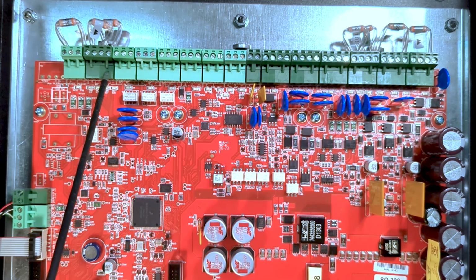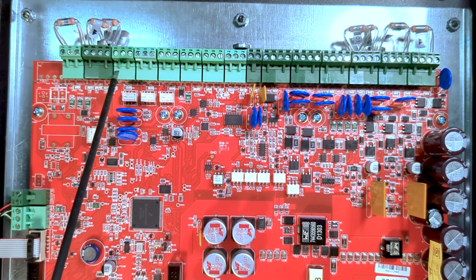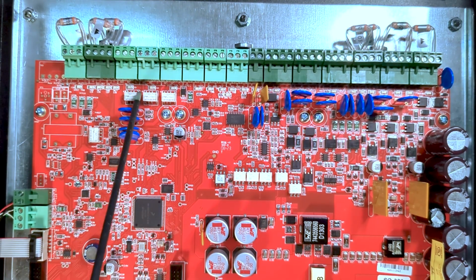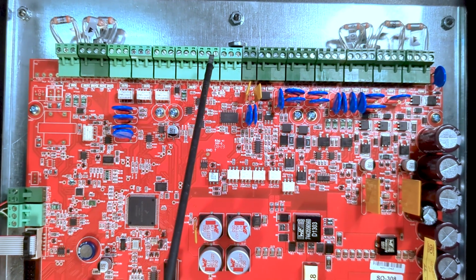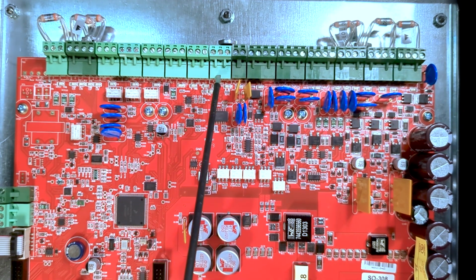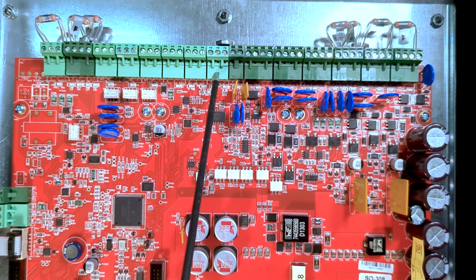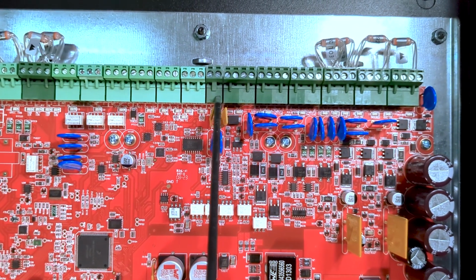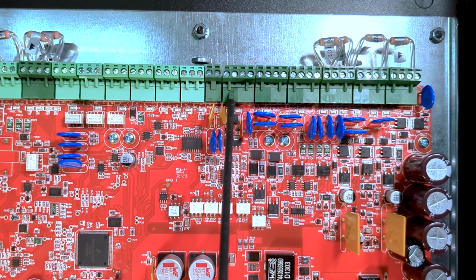We also have 2 relay inputs, which allow for panel activation, dedicated alarm contact, AC trouble, and common trouble relay contacts. Next, we have the RS-485 out and in connections to communicate with subsequent booster panels in Class A or Class B. Moving on, we have the 24-volt aux output, the signaling line circuit connection for compatible fire alarms.